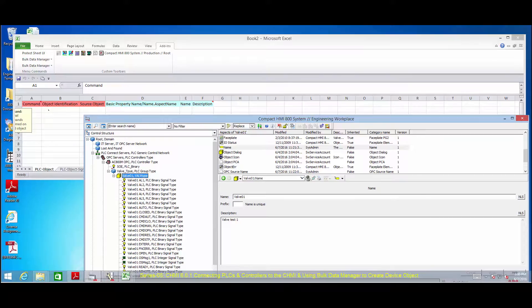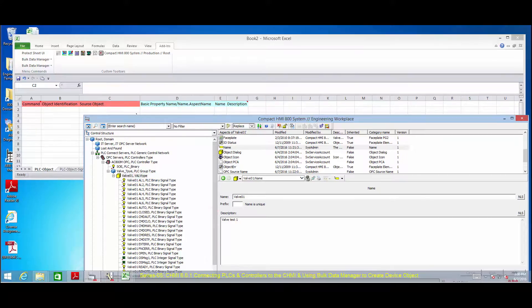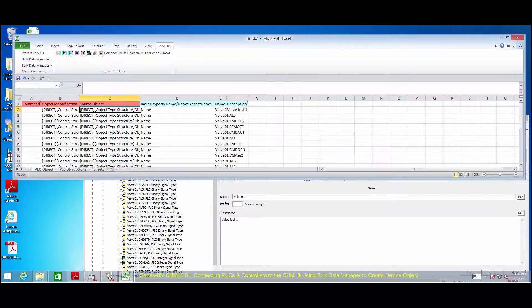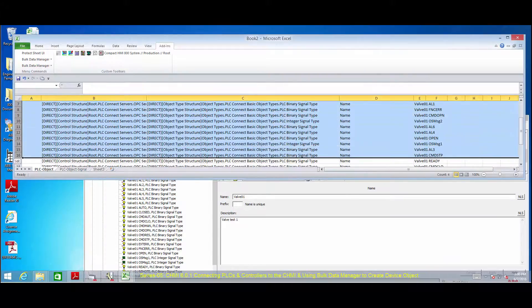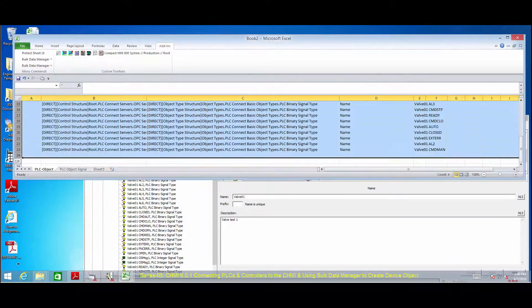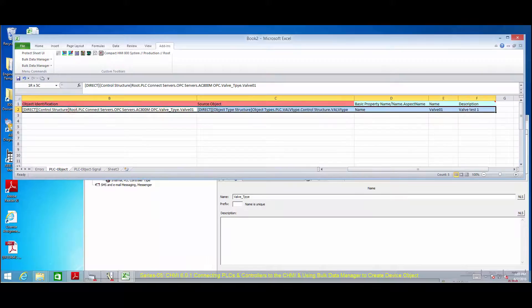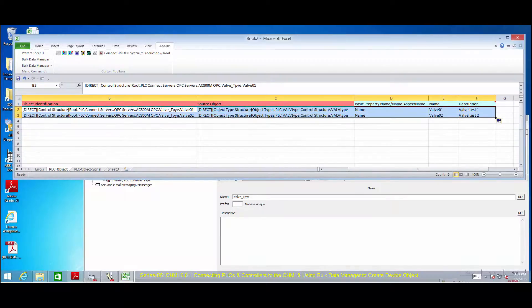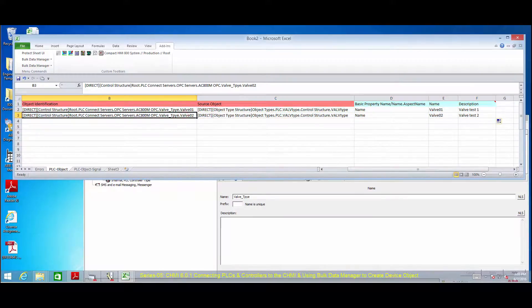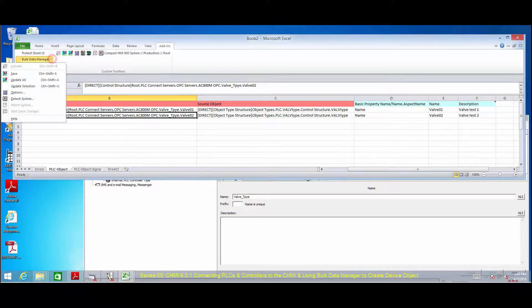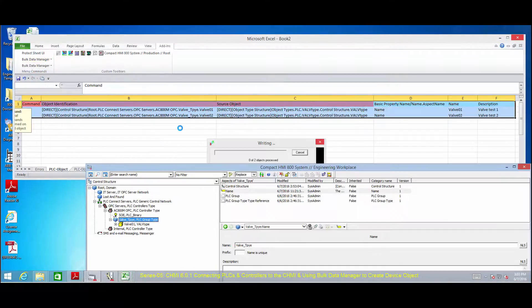Delete the rows that contain the signal connections. Configuration of the signals of the device object will be done in the second sheet of Excel. Use the drag feature of Excel and the Valve 02 object name is created. Simply save the BDM and you will notice that the Valve 02 device object is created in the control structure as shown.